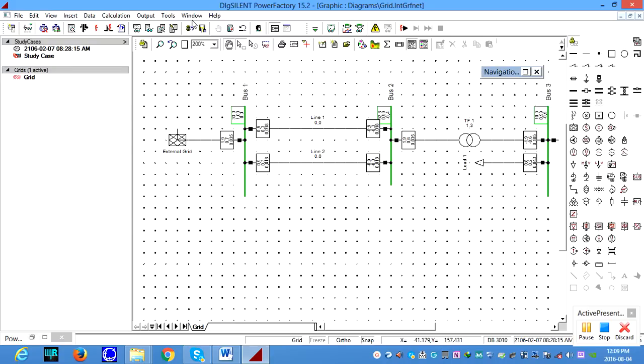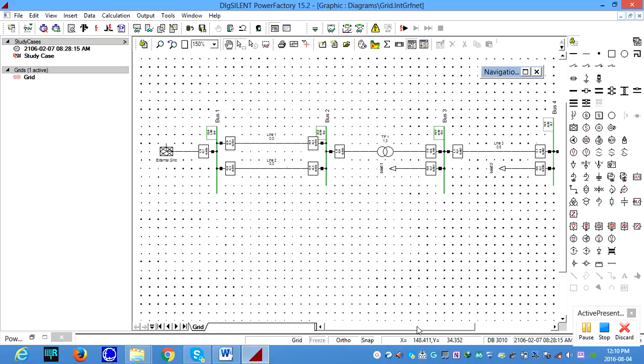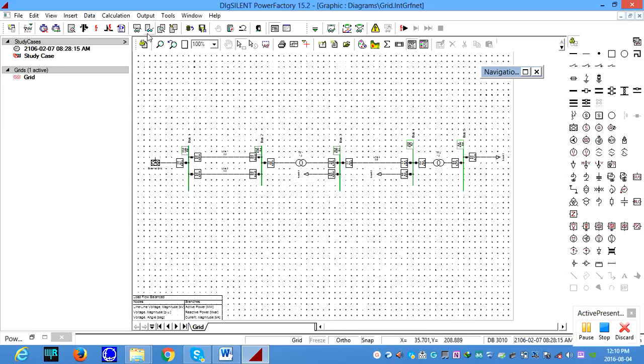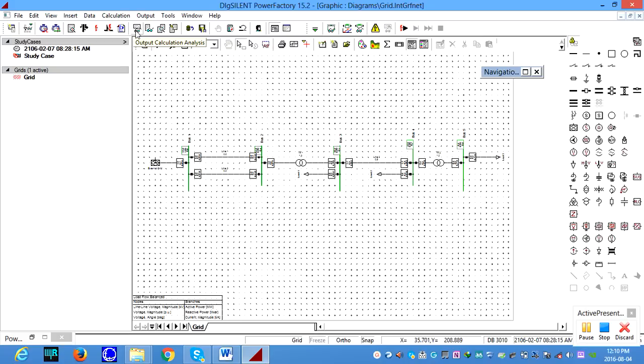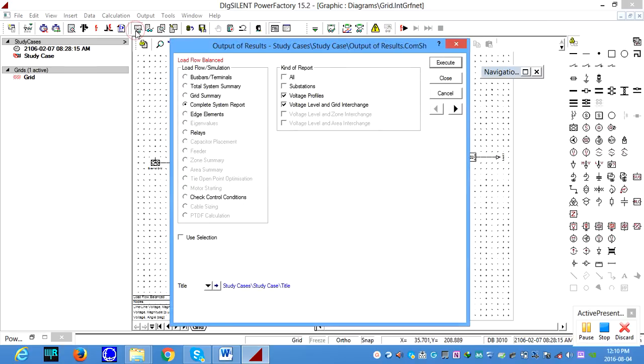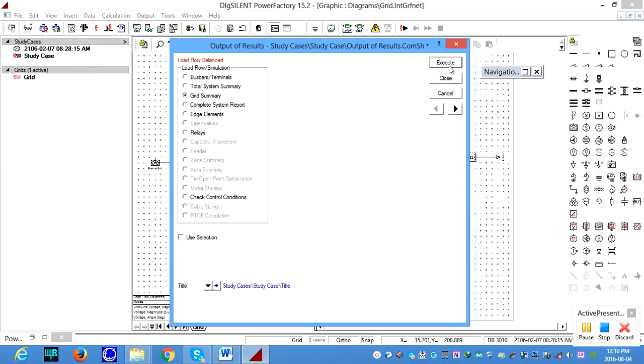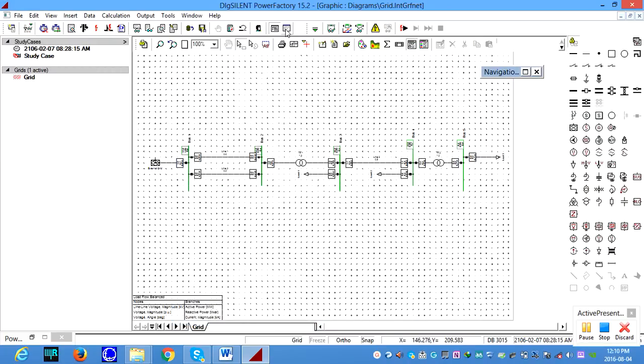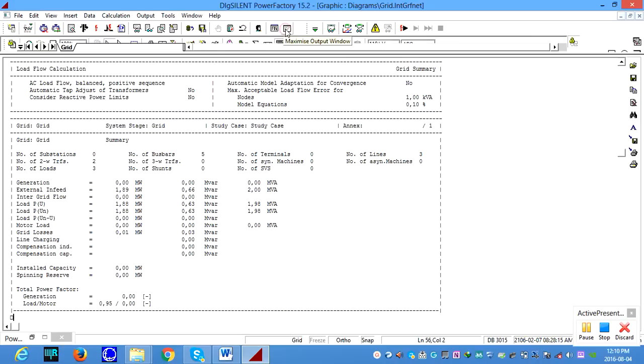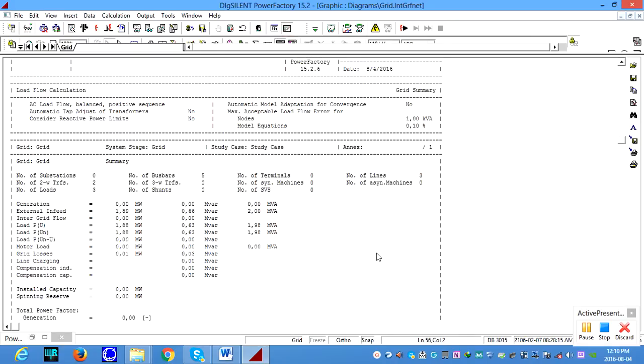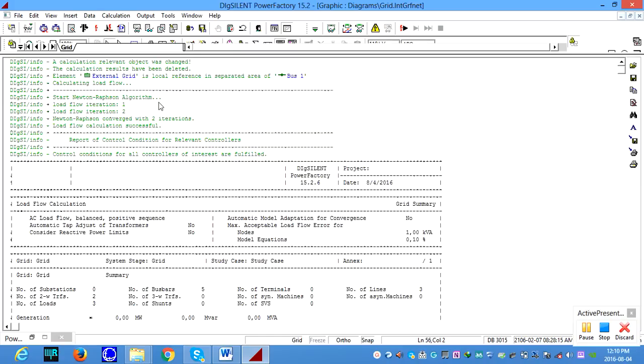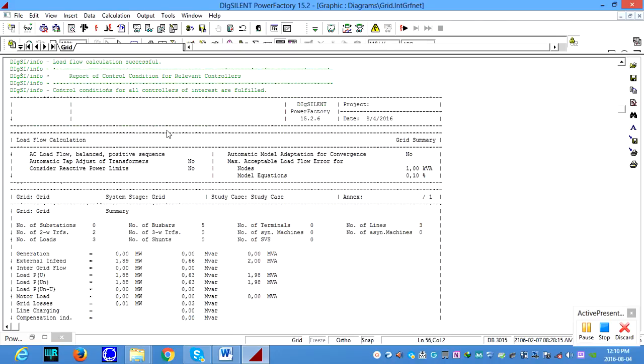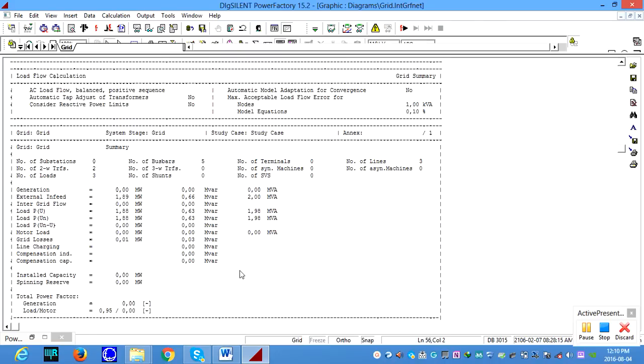Okay. Next, we need to validate the load flow results. To validate the load flow results, I just need to go to this one of the tools. You can see it's like a spec. They call it output calculation analysis. And if you click here, there are different options. If you want a grid summary, we can execute this one. Okay. Then this is the maximize output window icon. You can go to the output window and we validate. Let's see, this is using a Newton-Raphson load flow algorithm, and the computation converged within two iterations and the load flow is successful. And you can see the summary of the grid results.